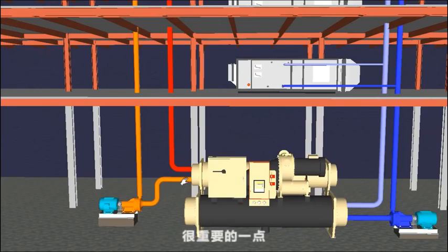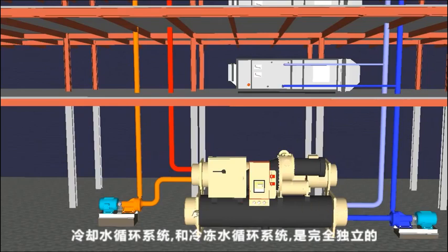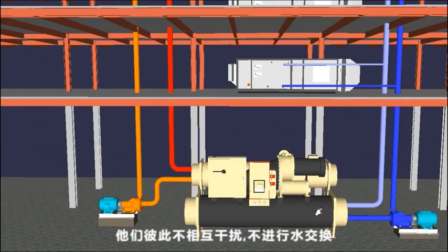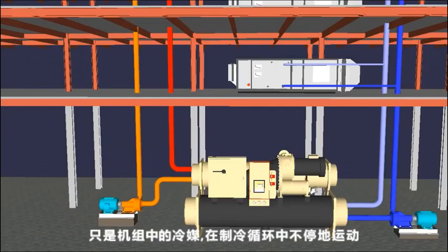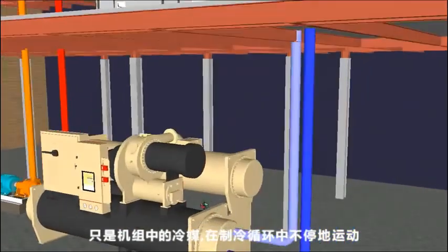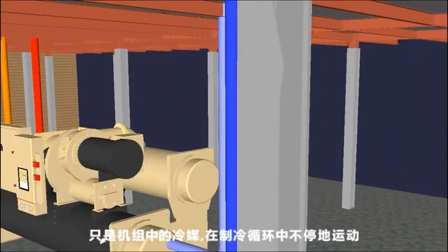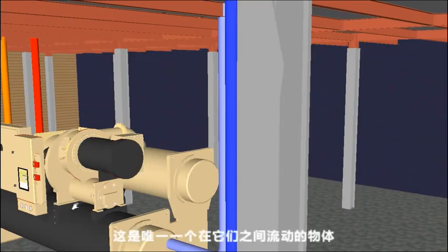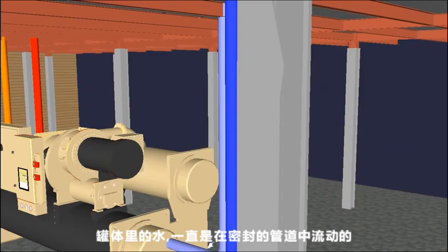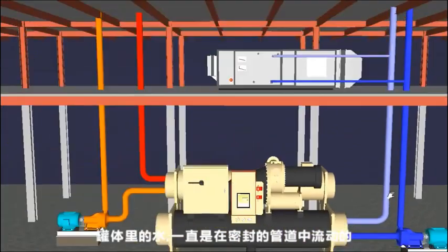It's important to note that this system here, the condenser water system and the chilled water system, are completely separated. They do not interact, they do not swap the water in between. It is just the refrigerant, which happens in the refrigeration cycle between these units. That's the only thing that passes between them. The water in here is sealed in tubes and leaves again through those pipes.